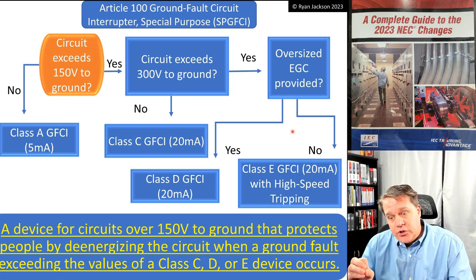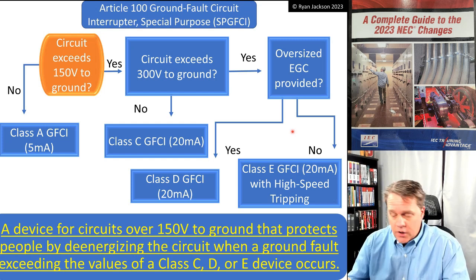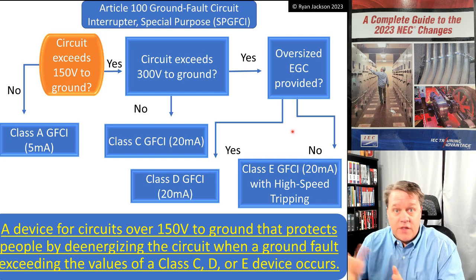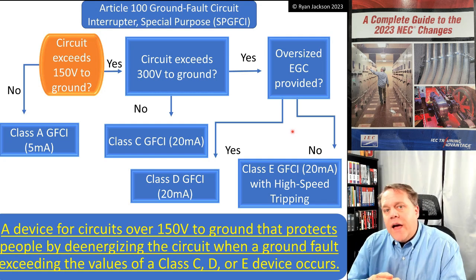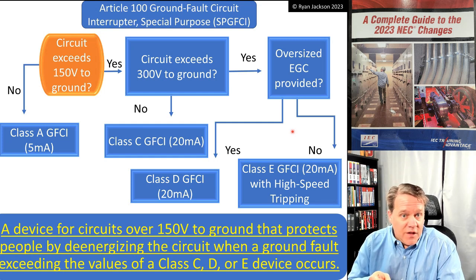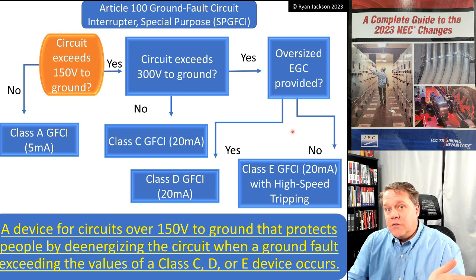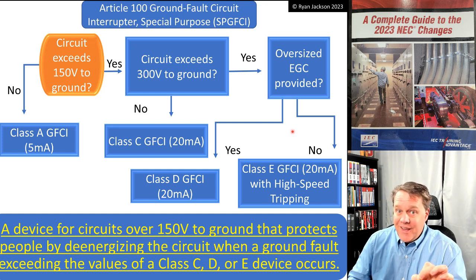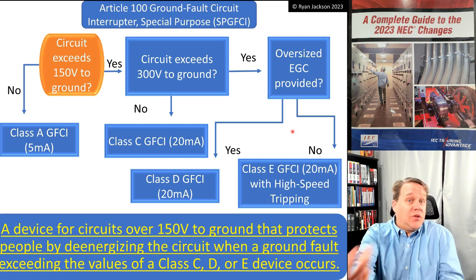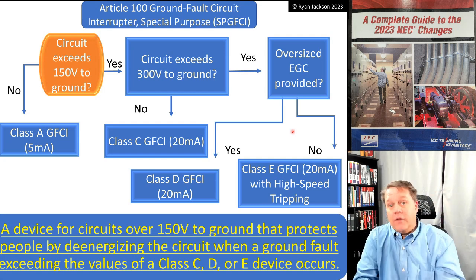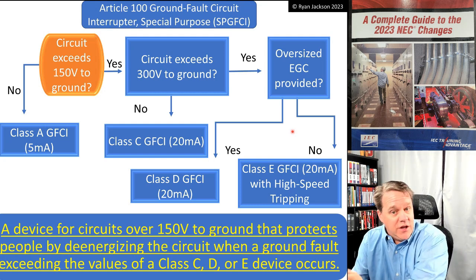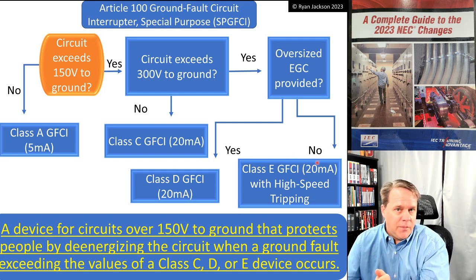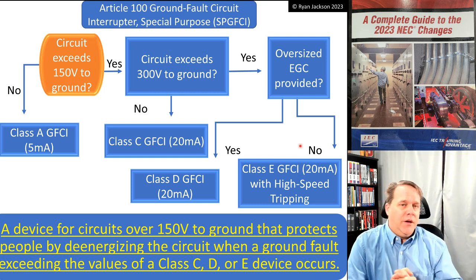When it comes to electric shock, what makes it fatal? It's the amount of current, the frequency of the circuit — 60 Hz and 10,000 Hz affect you differently — and most importantly, the duration of the shock. A GFCI does not limit how much current goes through your body; it limits how long that current flows through your body. It opens at four to six milliamps for Class A, but you can get a 30-milliamp shock for a very short duration. Same principle applies to Class C, D, and E.